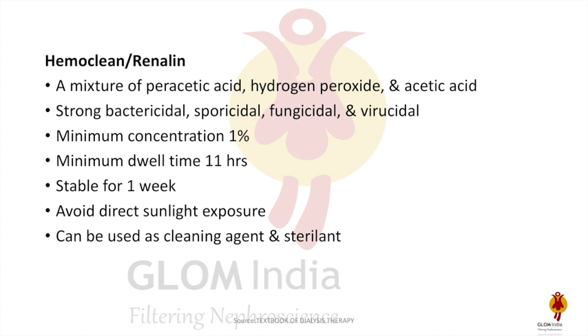In many centers, Hemoclean or Renalin are now in use. This is a mixture of peracetic acid, hydrogen peroxide, and acetic acid. It is strongly bactericidal, sporicidal, fungicidal, and virucidal. Its minimum concentration to be used is 1%. Its minimum dwell time is 11 hours — so if dialysis is to be initiated again within 11 hours, that dialyzer ideally should not be used. It is stable for one week and should be avoided from direct sunlight exposure.